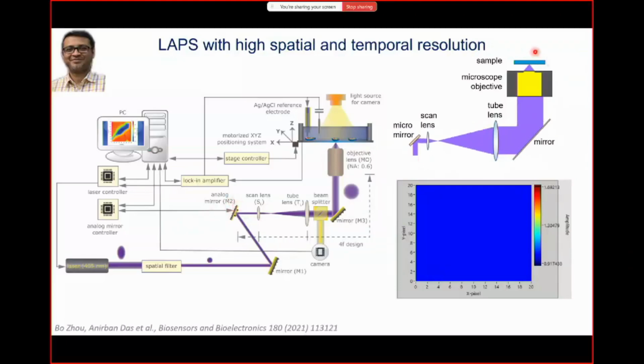You can see this enlarged in that little animation on the top. When you move the mirror, you also move the focus across the sample. This is a very precise 4F design that you also find in laser microscopes. You have a scan lens, a tube lens, and a microscope objective, which means you can scan the focus without degrading the resolution and without losing intensity. That's very important if you want to do imaging.